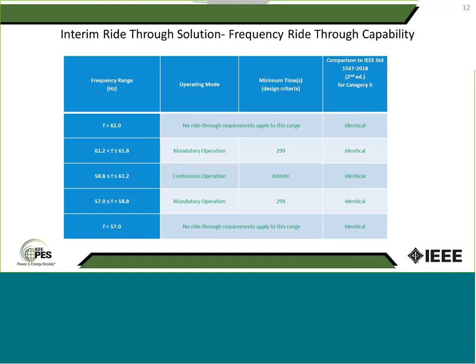Question about Massachusetts. Do the new ride-through standards require changing settings on existing inverters en masse, or do they only apply to new installs? Only applies to new installs. We set a date of March 1st for any inverters or any solar applications that we receive after March 1st, and that are larger than 100 kilowatts. And then June 1st was the date that any solar applications received on or after June 1st, regardless of size, will comply with the ride-through requirements.